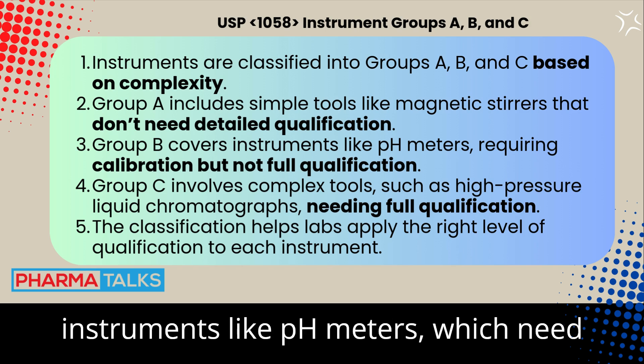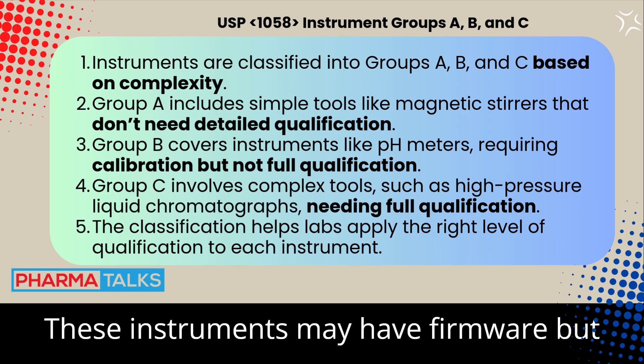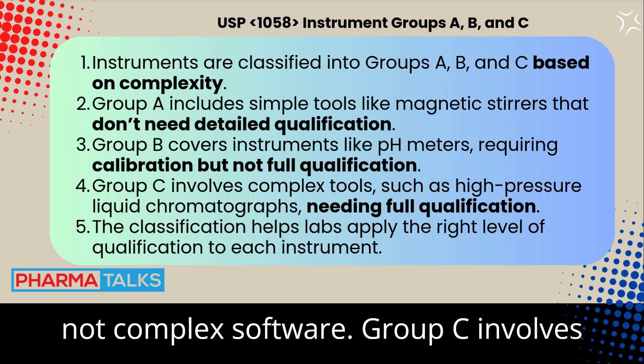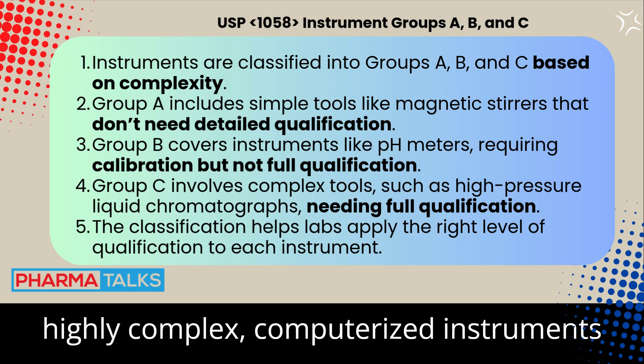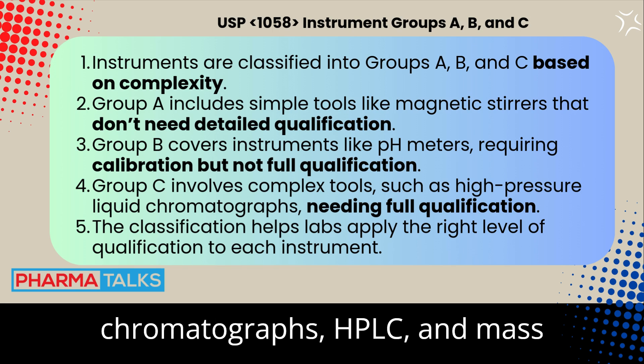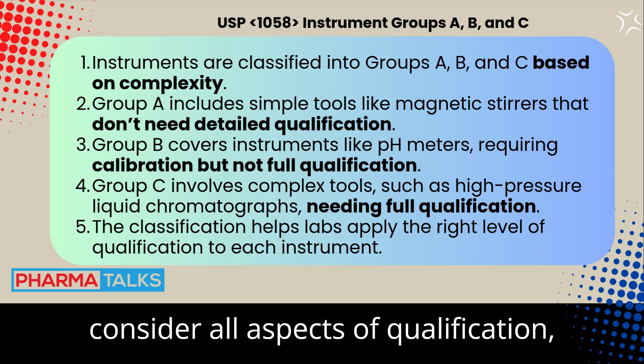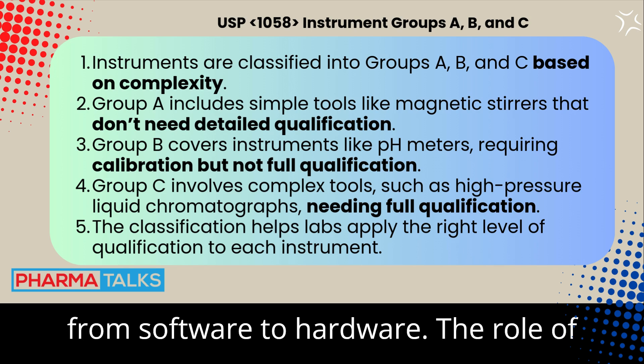Group B covers instruments like pH meters, which need calibration but not full qualification. These instruments may have firmware but not complex software. Group C involves highly complex, computerized instruments such as high-performance liquid chromatographs (HPLC) and mass spectrometers. For these, you need to consider all aspects of qualification, from software to hardware.